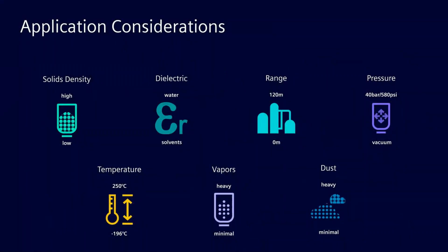Radar technology is not affected by process conditions like many other technologies are. Harsh environments in liquids or solid applications are not a problem. Material density or dielectric, process pressure and temperature do not impact the measurement. Even heavy vapors or liquids or heavy dust and solids are not an issue in most cases.